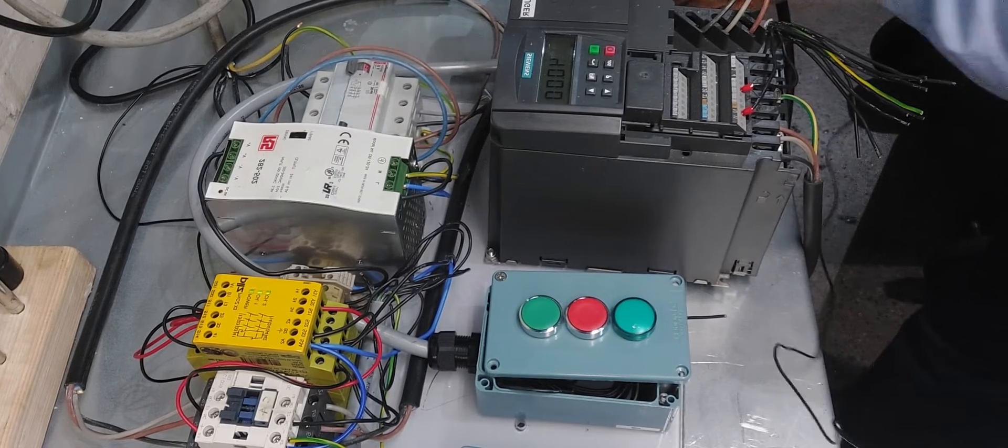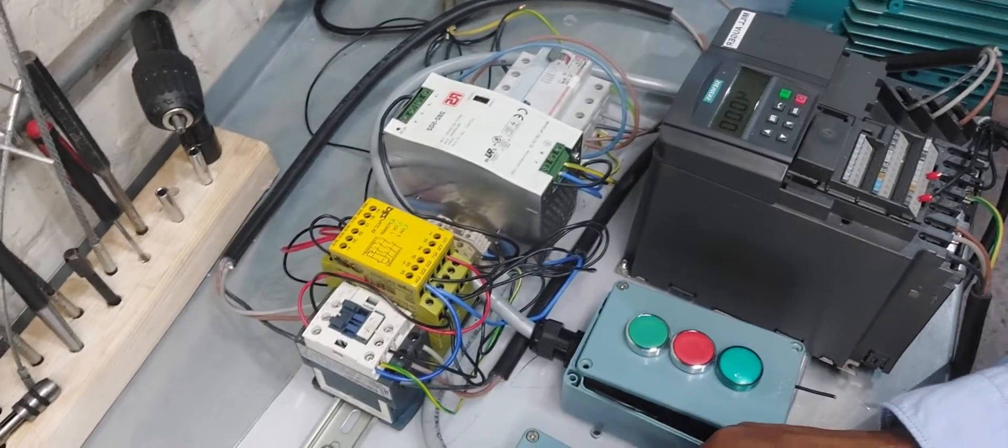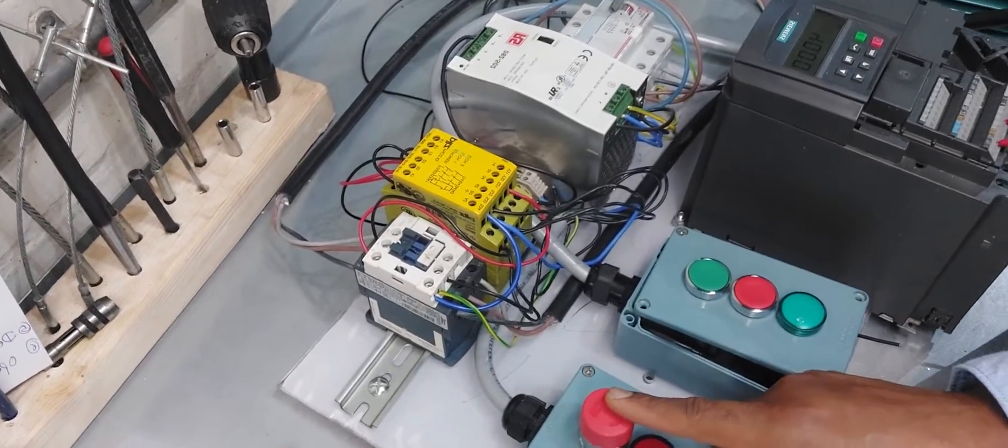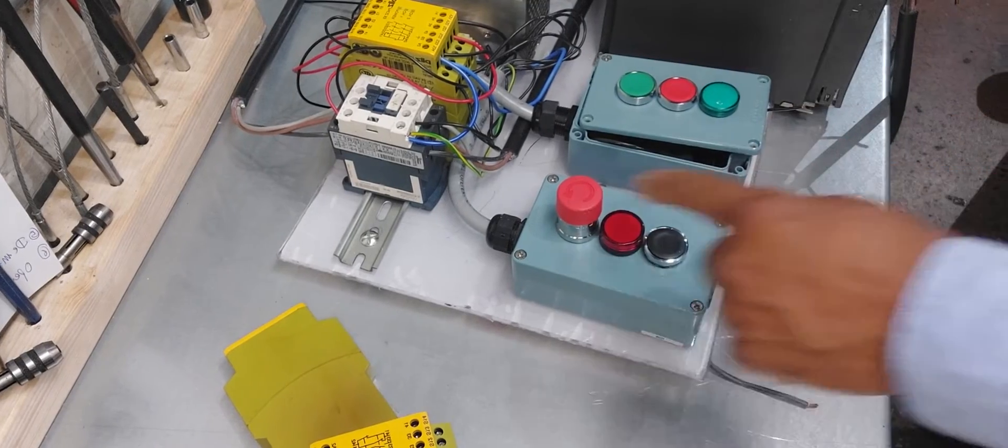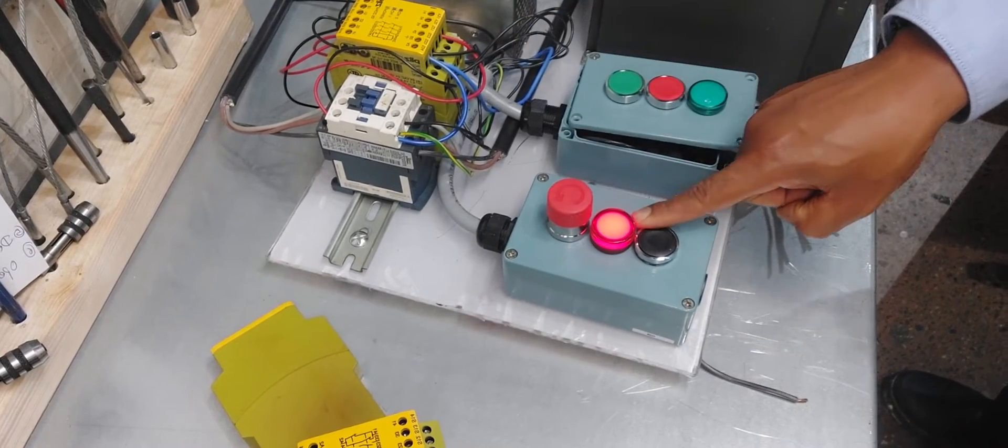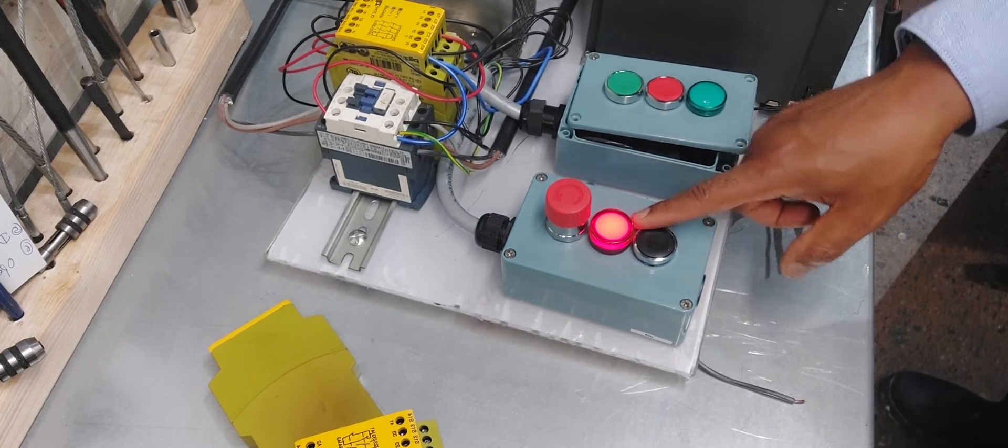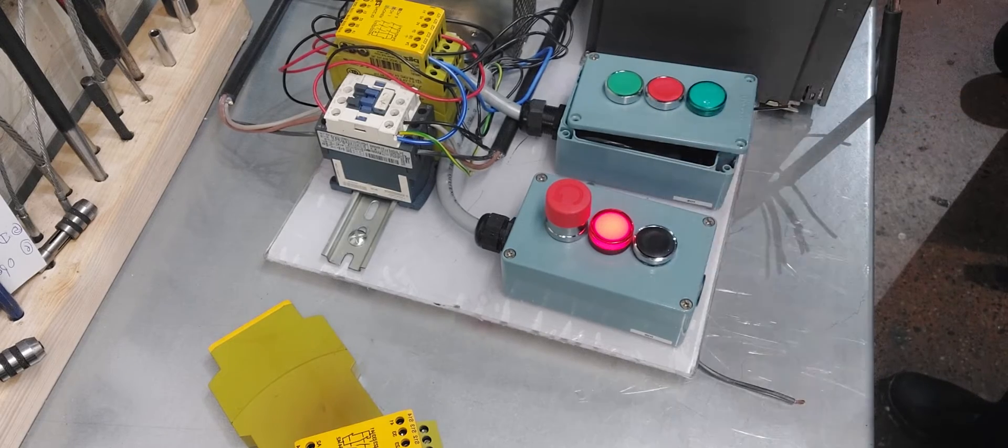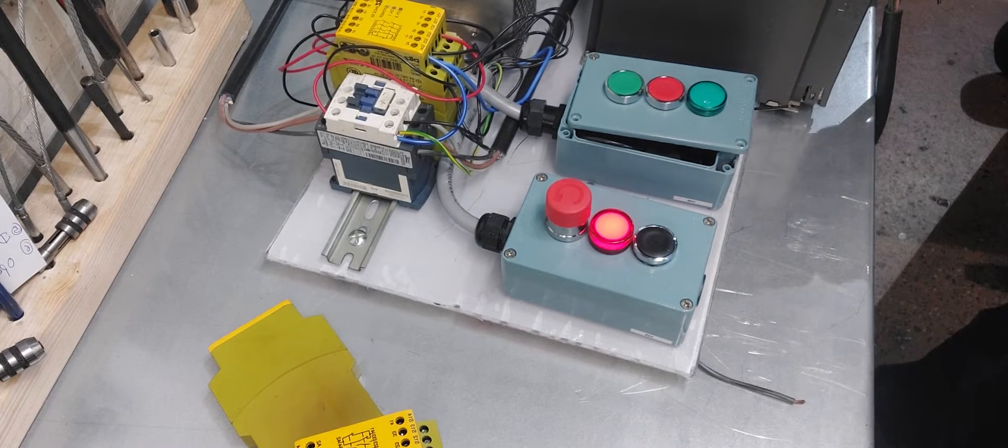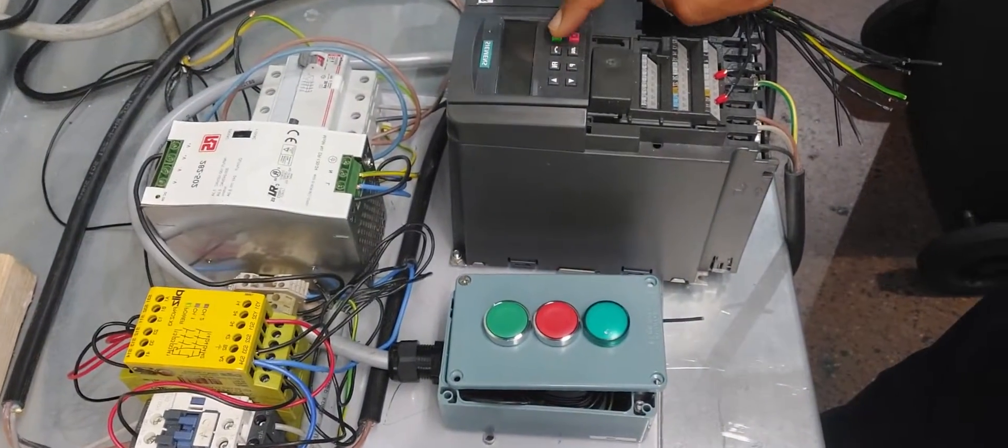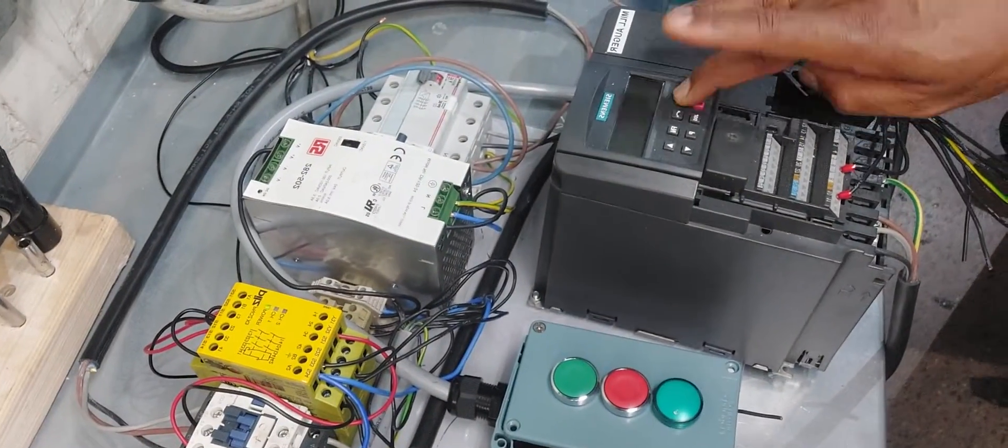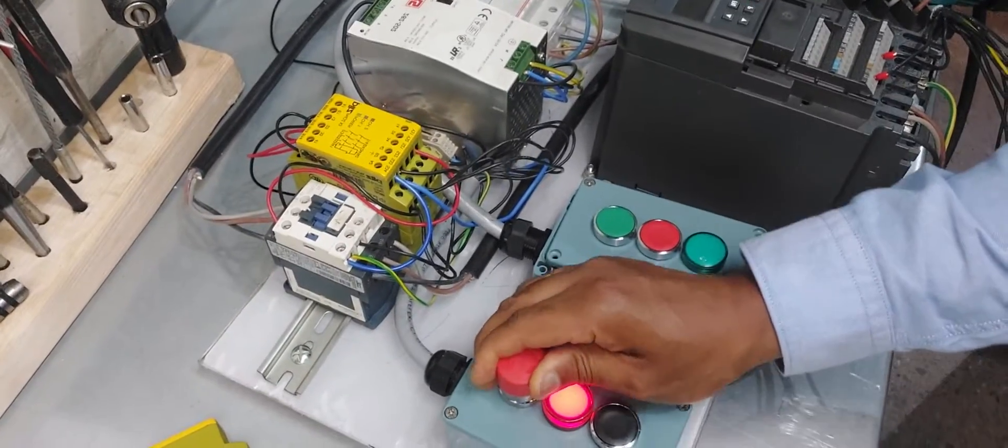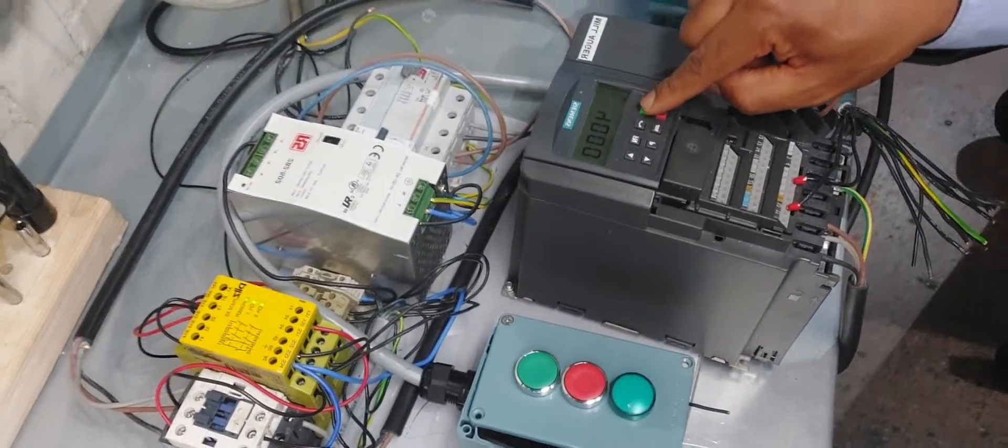Once you push it, the motor is running. But once you push the emergency stop because there's a problem, that light comes on and tells you the safety barrier has been broken. This helps for quicker troubleshooting. You cannot operate anything until the system has been reset.